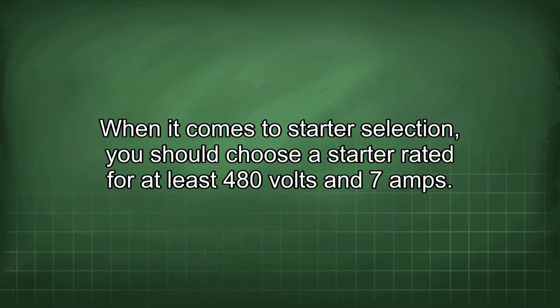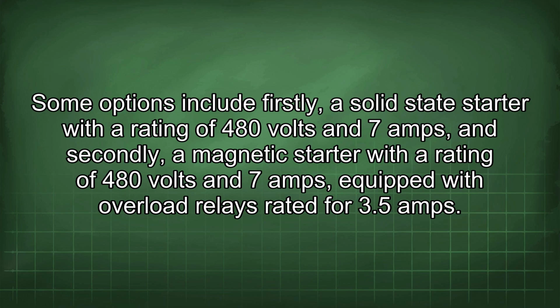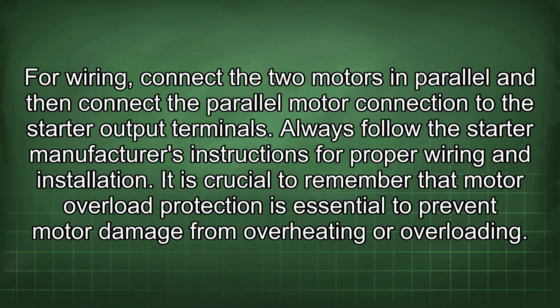When it comes to starter selection, you should choose a starter rated for at least 480 volts and 7 amps. Some options include, firstly, a solid-state starter with a rating of 480 volts and 7 amps, and secondly, a magnetic starter with a rating of 480 volts and 7 amps, equipped with overload relays rated for 3.5 amps. For wiring, connect the two motors in parallel and then connect the parallel motor connection to the starter output terminals. Always follow the starter manufacturer's instructions for proper wiring and installation.